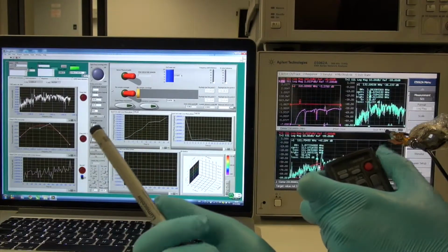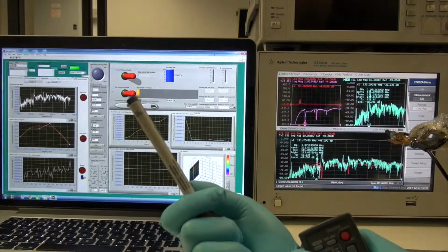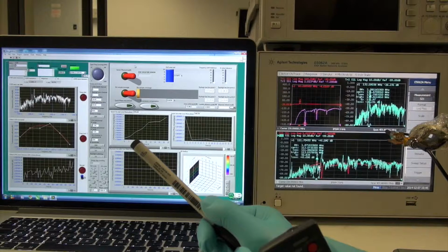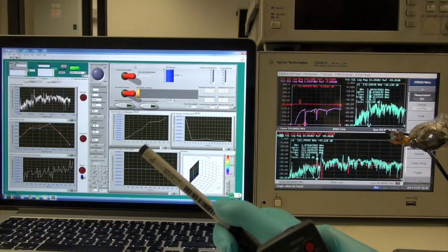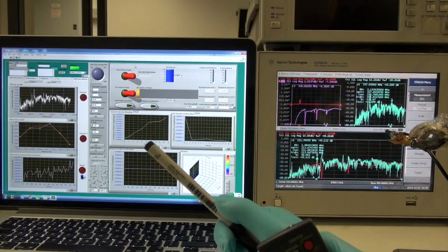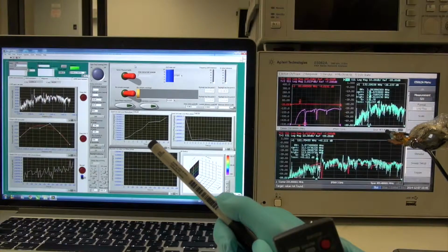Okay. In the device diagnosis panel, the first function is the device health diagnosis function. This function is based on measuring the zinc oxide layer condition.